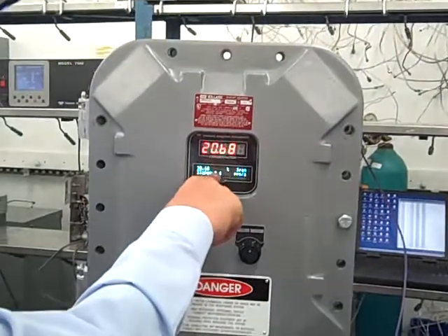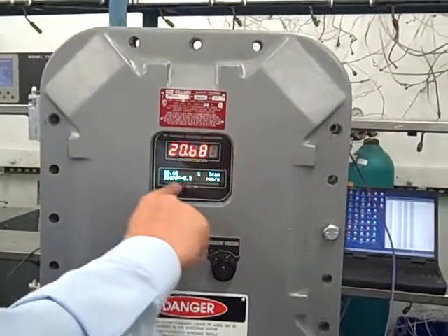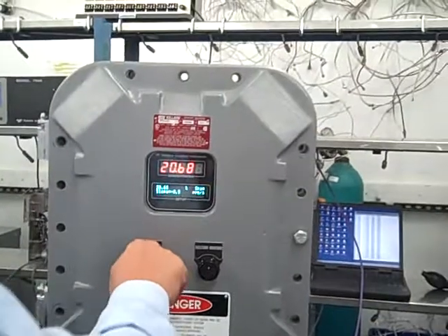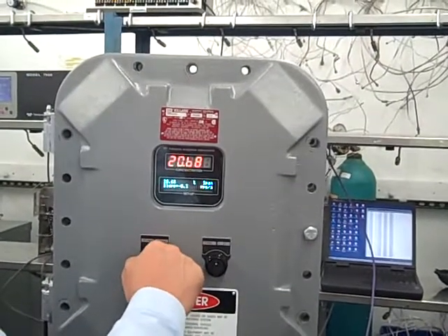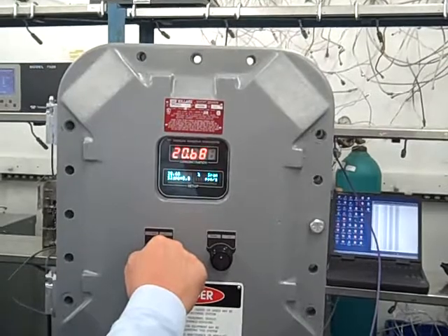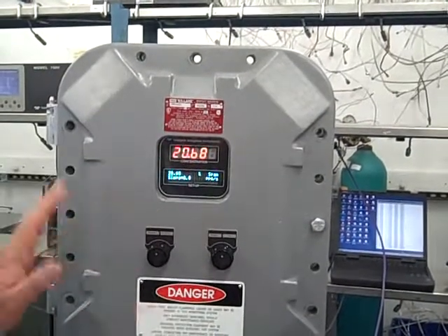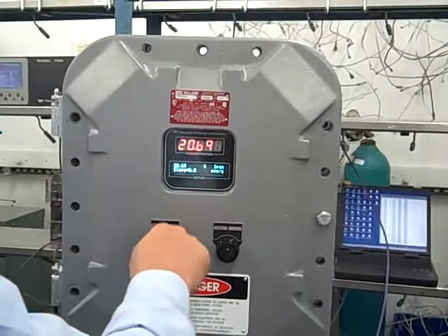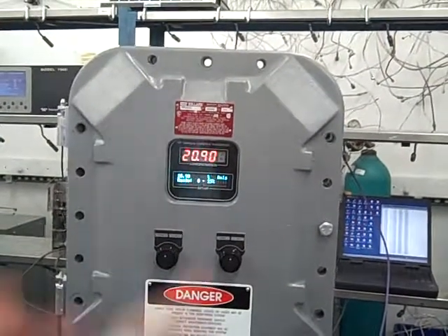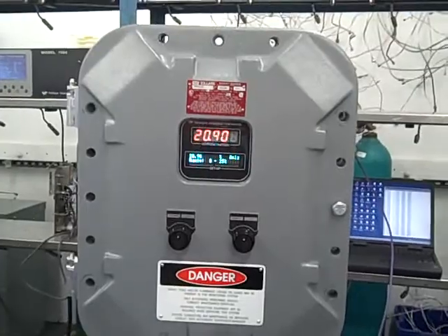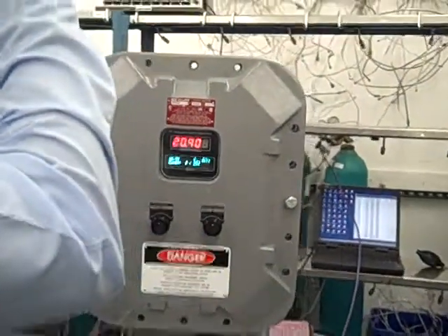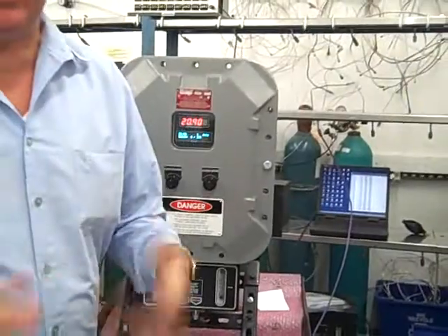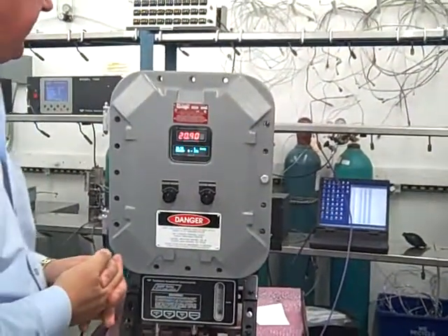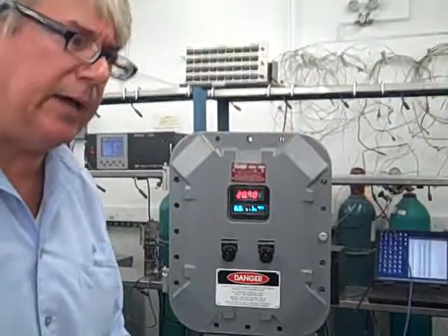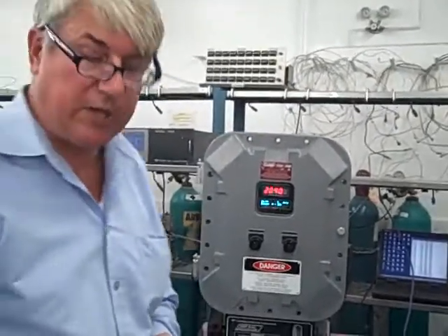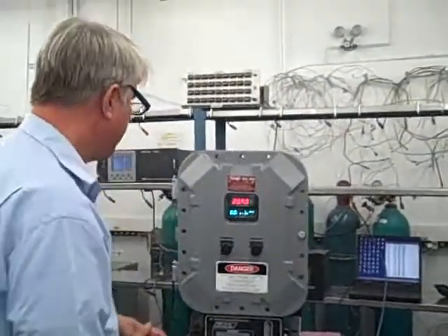Now this tells you basically when the reading is stable. This is an indication, the slope value, of when the reading's stable. So we go ahead and say yes. Now the slope went to 0. You don't have to wait for it to reach 0, but it's a good indicator. So we go ahead and say now it's stable. And boom, done. Calibration done. Okay, it's that simple. And typically people always ask how often you should calibrate. I typically recommend calibrating once a week or something like that, but the sensors are typically very stable. Some customers get by with once a month with no problem.